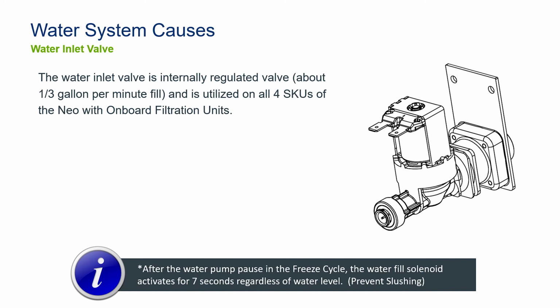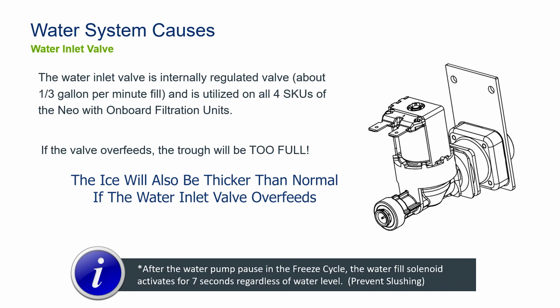Well, if that water valve is feeding in 2/3 of a gallon a minute, that's going to lead to a big problem for you. If this valve overfeeds, the trough will be too full, and it will take more water to convert into ice. You may stay in freeze too long. This will be especially true in situations where maybe the water's too warm, and you have to keep pulling out more heat than you planned on.